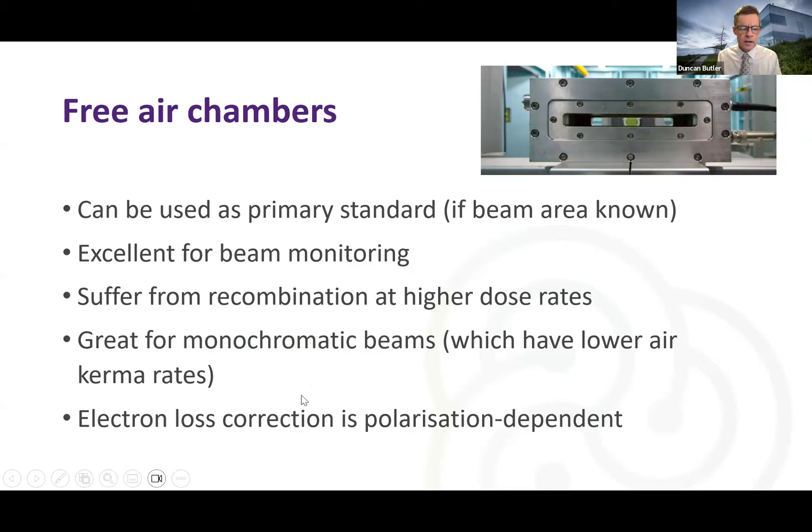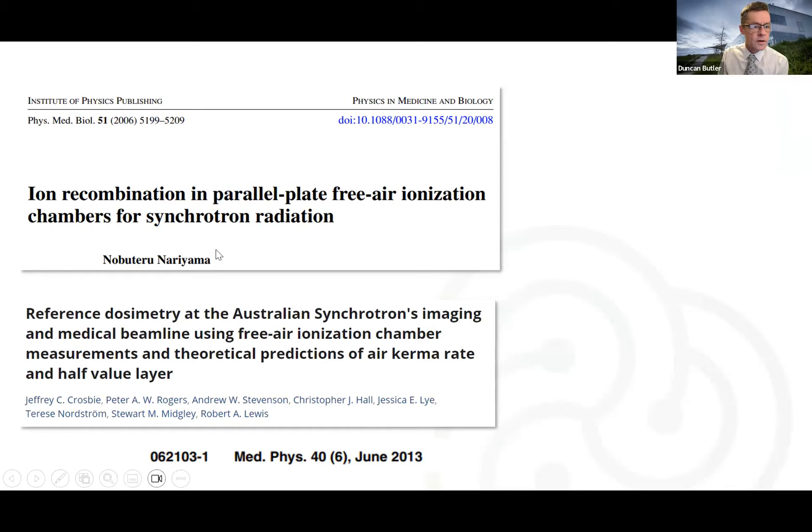They do have an electron loss correction. If you're using them as a primary standard, you want every secondary electron created in the air gap. You don't want them to reach the plates. And so you have to calculate what the loss is. And it turns out that depends on the polarization. And it's different for photoelectric and Compton. So it's quite a complicated calculation and most codes just assume random polarization. So to calculate that accurately can be problematic. But I will leave a couple of references here, one to a paper by Nariyama which talks about the polarization as well, and where Jeff Crosbie and Jess Lye used the primary standard on Australia's beamline.